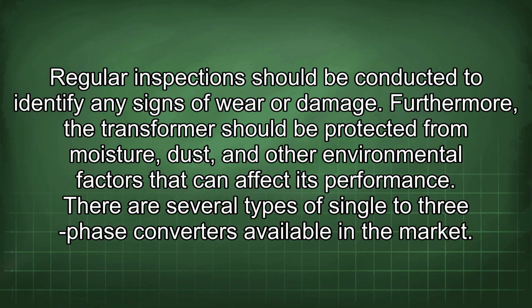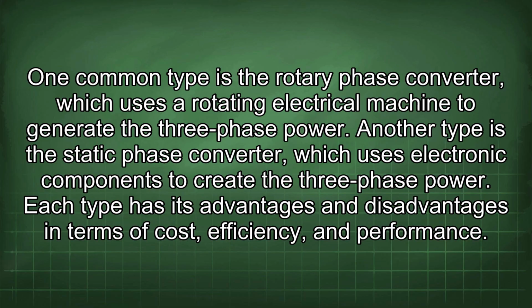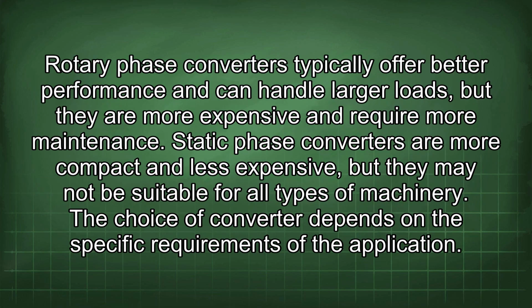There are several types of single to three-phase converters available in the market. One common type is the rotary phase converter, which uses a rotating electrical machine to generate the three-phase power. Another type is the static phase converter, which uses electronic components to create the three-phase power. Each type has its advantages and disadvantages in terms of cost, efficiency, and performance. Rotary phase converters typically offer better performance and can handle larger loads, but they are more expensive and require more maintenance. Static phase converters are more compact and less expensive, but they may not be suitable for all types of machinery. The choice of converter depends on the specific requirements of the application.